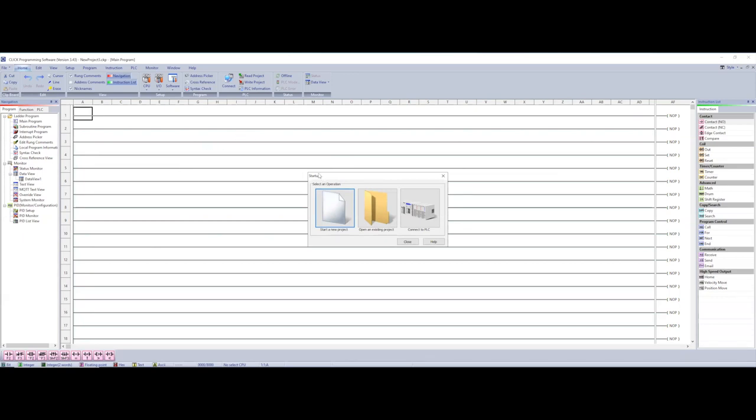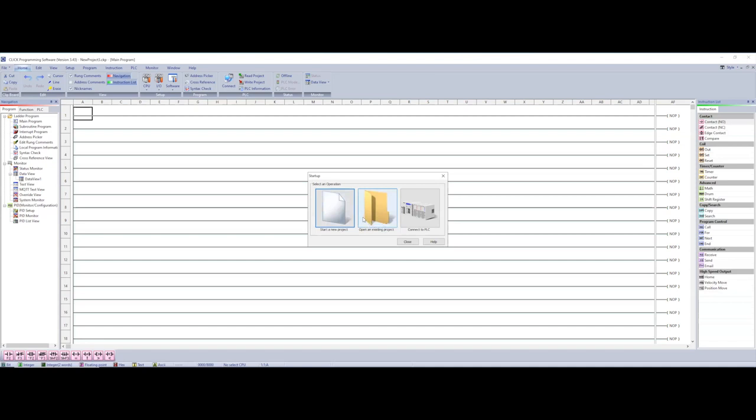Okay so here's how we get started. You notice on the startup screen you've got three different options here. You can start a new project which we could do at this point but I'm going to show you another way to do it which I think is a little easier especially if you've got your PLC and it's already connected to your computer. You can open an existing project obviously if you've already got a project or you can connect to the PLC. This is what we're going to do and the reason for that is because you don't have to worry about setting up your PLC to the correct model number and everything else. This will do it for you.